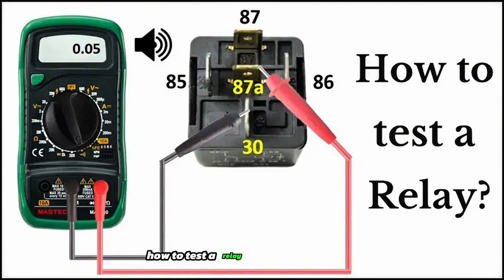How to test a relay. Turn off all power. Visually inspect it. Many relays are clear plastic. You can see if the contacts are stuck. Check the coil resistance the same way. Use jumper wires to apply 24 volts and see if the relay closes. Use your meter to test continuity across the contacts, with and without coil power. If the coil works, but the contacts don't pass power, replace the relay.